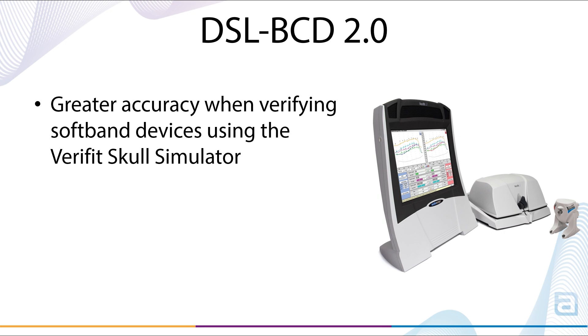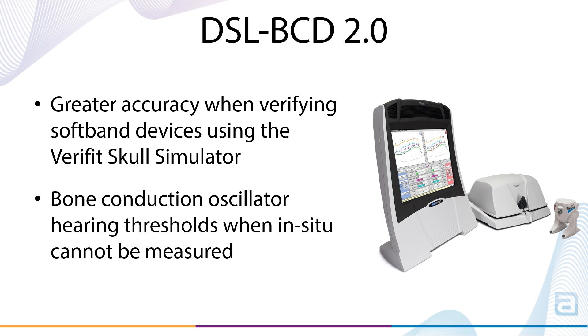DSL-BCD 2.0 prescriptive targets for bone conduction device verification using the Skull Simulator enables greater accuracy for softband-fitted BCDs and provides the flexibility to use standard bone oscillator audiometric thresholds when in-situ thresholds cannot be measured via the bone conduction device and the hearing aid fitting software.